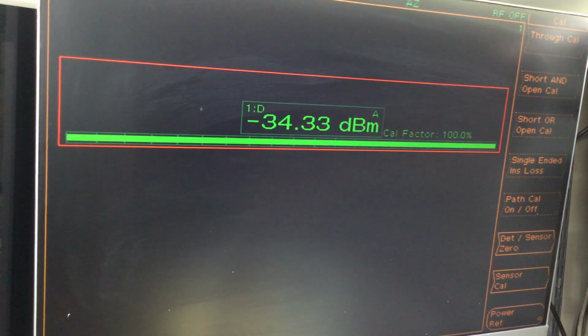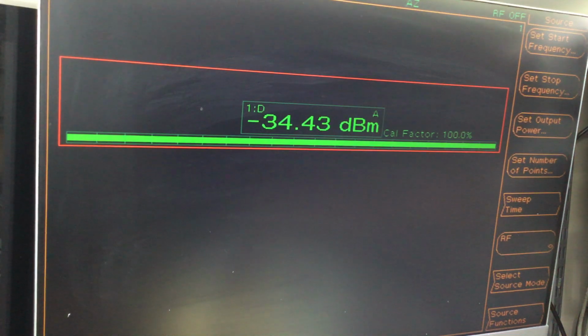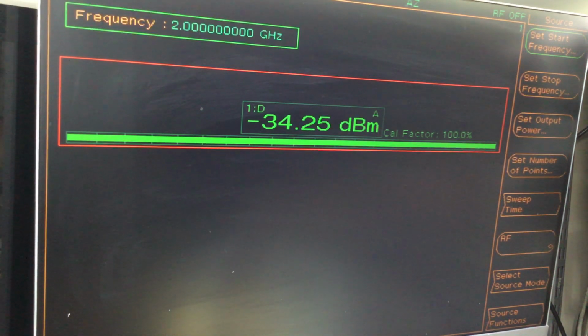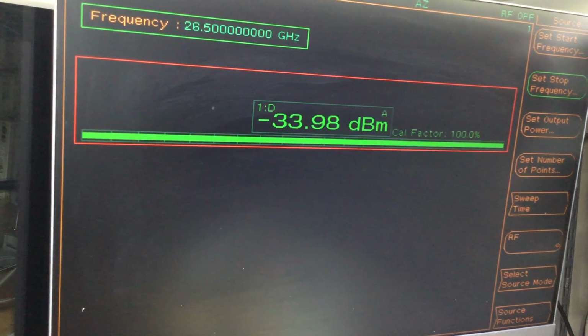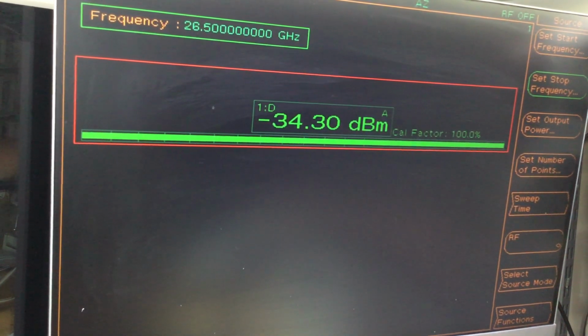So we're going to go to set the start frequency, and because this particular probe has a frequency range of, if I just have a look very carefully at the label, obviously we'll say 50 megahertz. We'll put that in then, so 50 megahertz, and then we'll set a stop frequency of, let's see now, 26.5. It's already in, so I don't need to mess about with that.